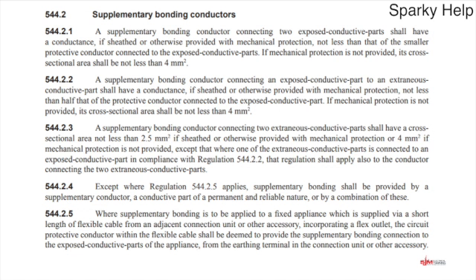Probably why they put 6mm in is because 6mm is what they have and they don't have 4mm with them, but it's perfectly acceptable, as long as it's 4mm or larger. But obviously if you're going to bother to put conduit in between the pipes, then you could get away with putting 2.5, but if you've got time to put conduit in between the pipes, well done you.